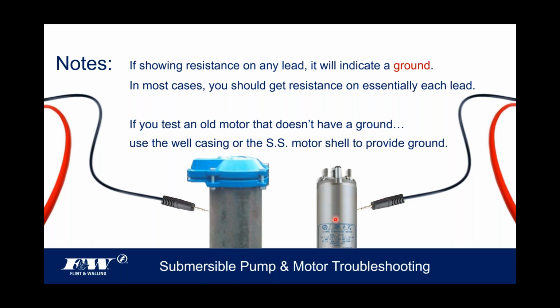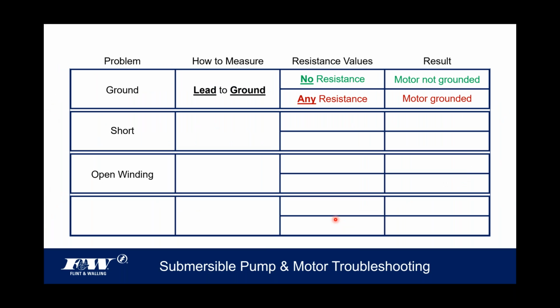If you happen to have the pump and motor out of the well, you can, again, on the side of that motor shell, that stainless steel, create a nice ground there, and you can determine whether the motor is grounded or not. So up here at the top, again, if we're going to check for a ground, we go lead to ground, each lead to ground. If there's no resistance, the motor is not grounded. If there's any resistance at all, that indicates the motor is grounded.